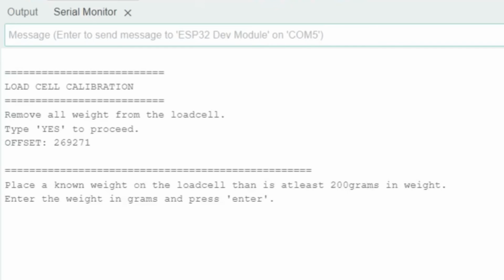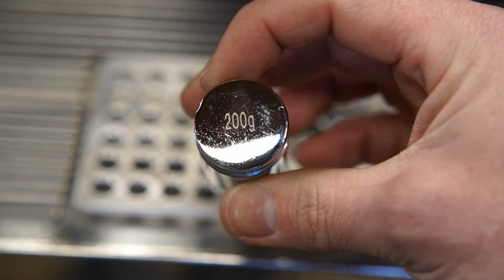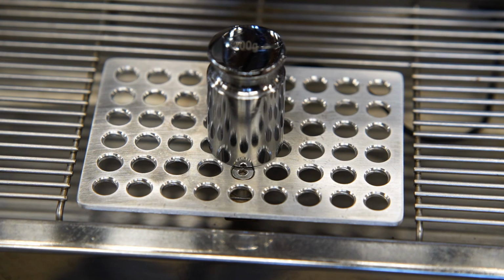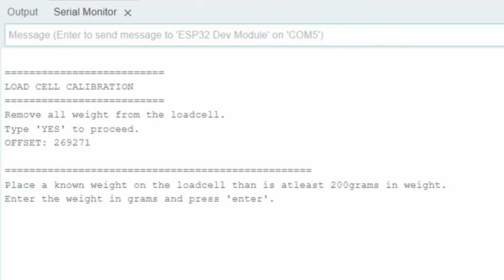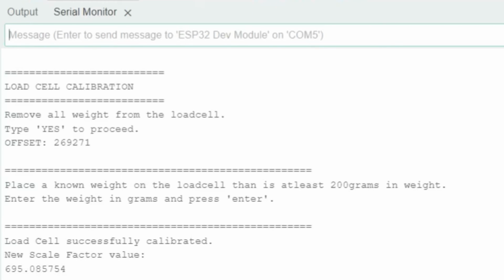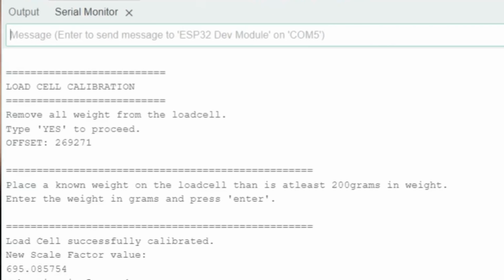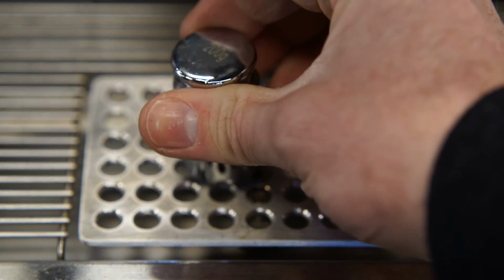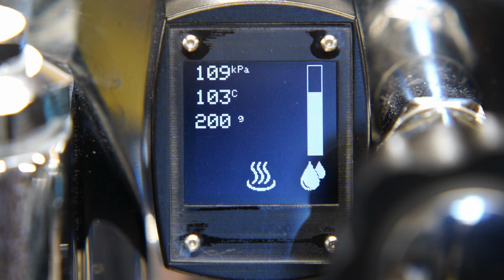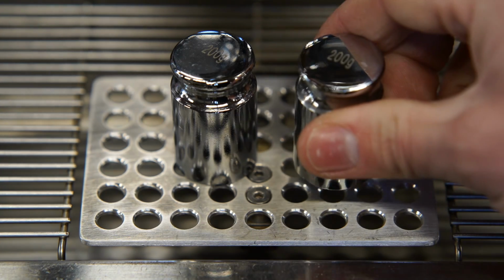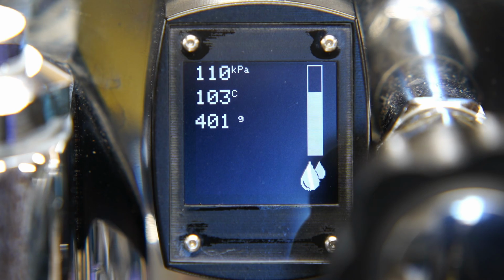Next, I'm asked to place a measured weight on the load cell that is at least 200 grams in weight. I'm using this 200 gram scale weight, and I'm placing it on my load cell. Next, I enter the weight in grams, which in this case is 200. And just like that, the load cell has been successfully calibrated. I can verify that the calibration has been successful by placing any amount of weight on the scale and comparing it to the value on the display.